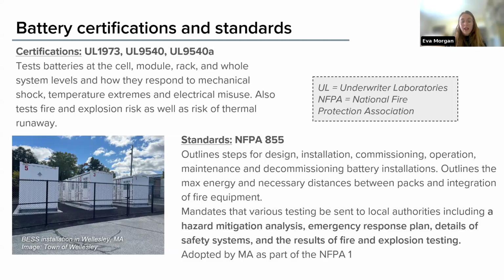One important aspect of the NFPA 855 is it mandates communication between developers and local authorities, including the dissemination of hazard mitigation analysis, an emergency response plan, the safety system details, and the results of fire and explosion testing. In Massachusetts, our fire code has adopted the NFPA 1, which includes the NFPA 855.